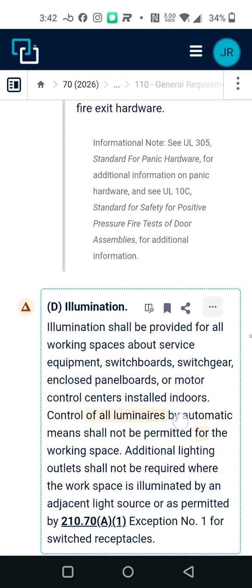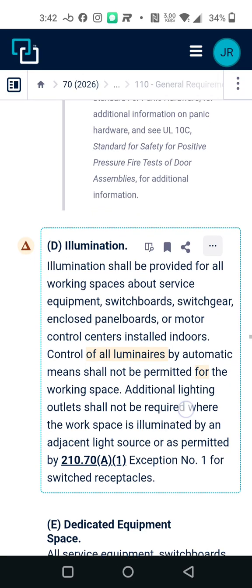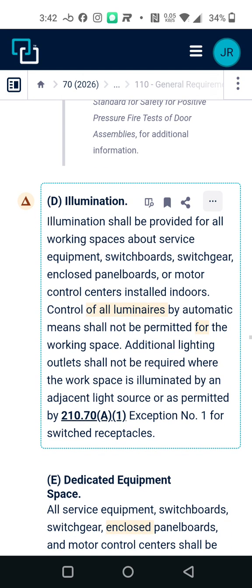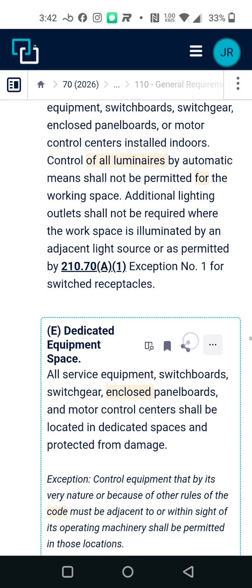Illumination should be provided for all working spaces about service equipment, switchboards, switchgear, enclosed panelboards or motor control centers installed indoors. Control of all luminaires by automatic means should not be permitted for the working space. Additional lighting outlets should not be required where the working space is illuminated by an adjacent light source or as permitted by 210.70(A)(1), exception number 1 for switched receptacles.